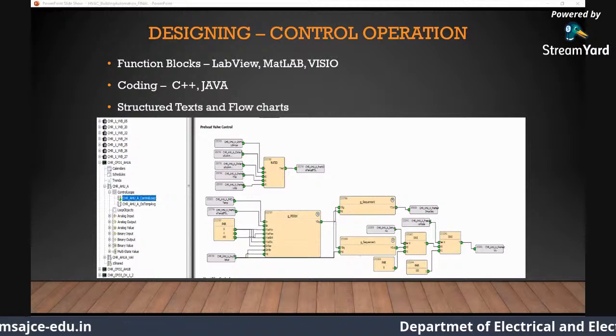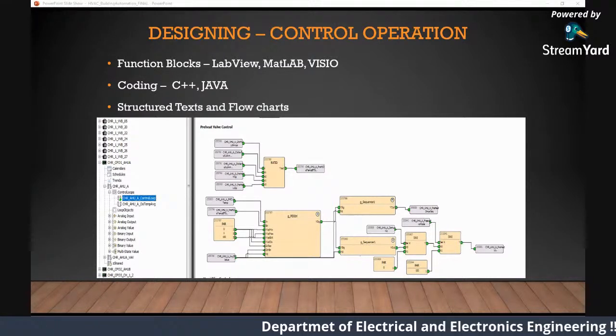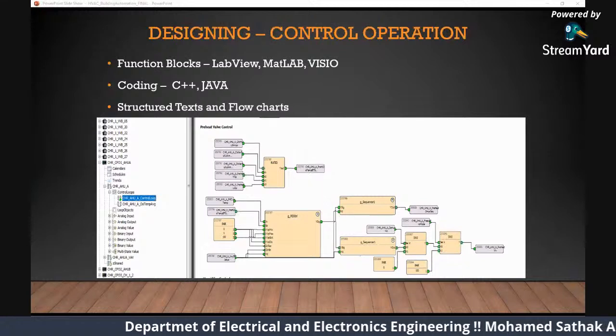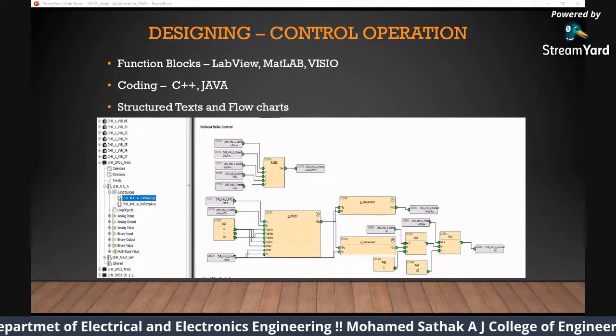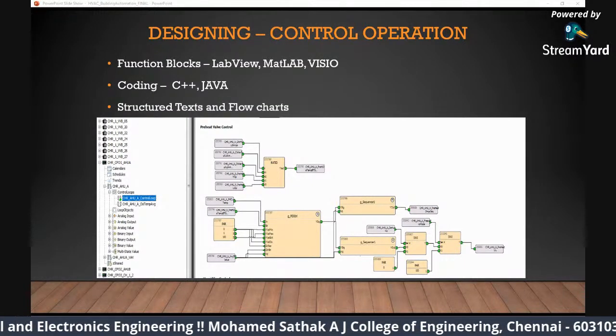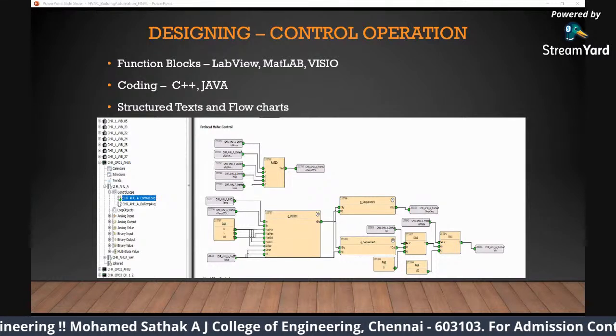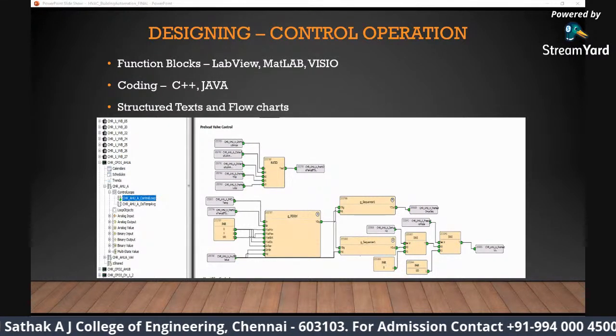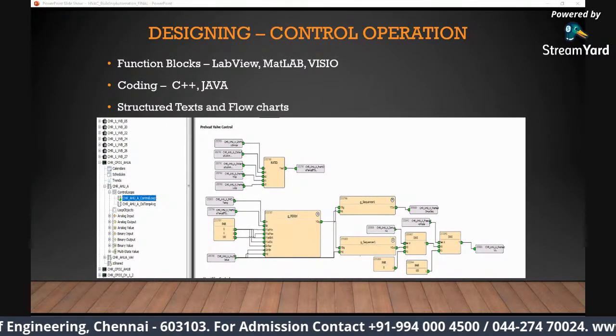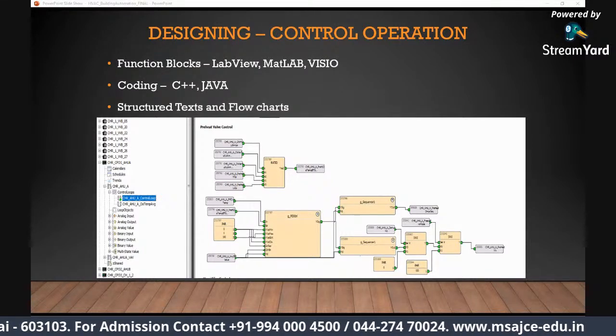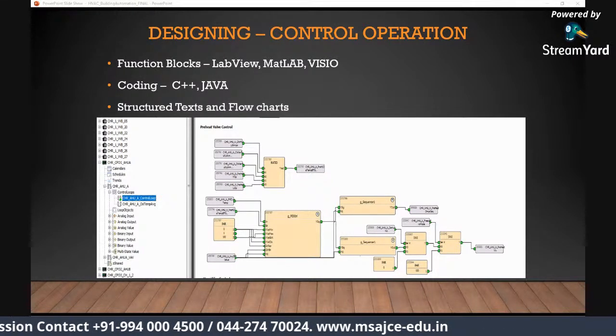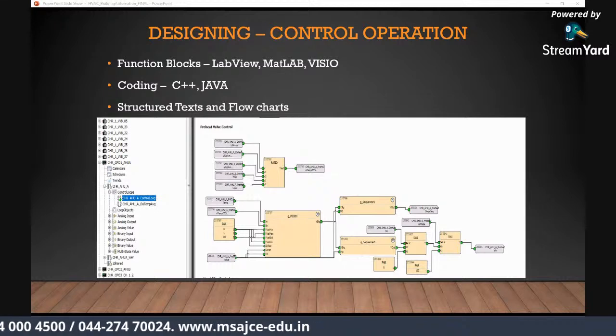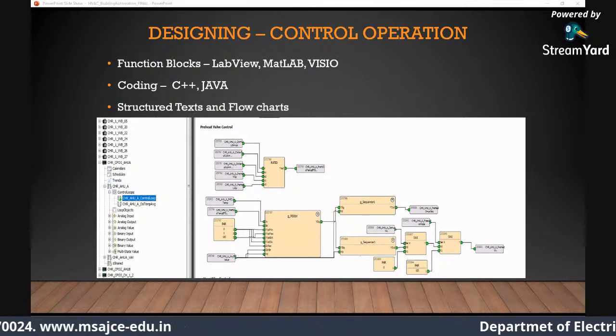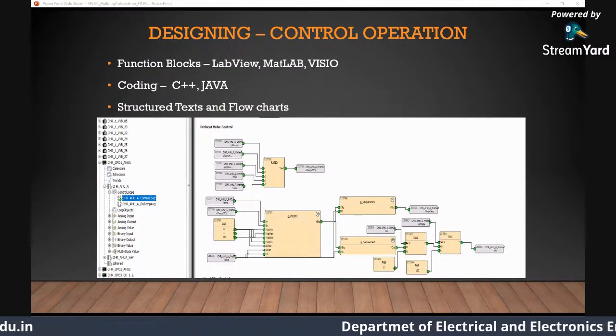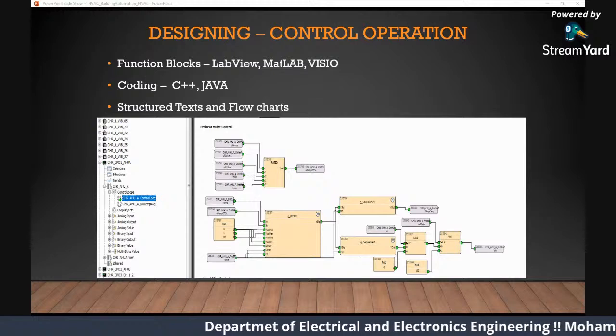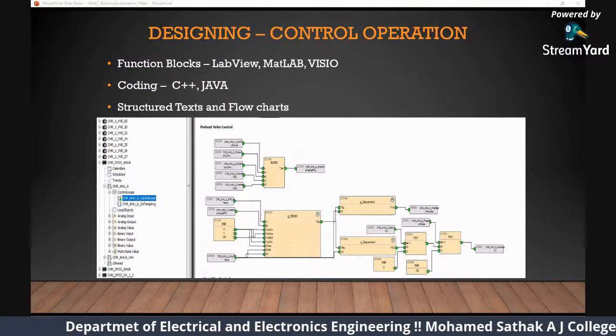Not every building will have one AHU, one chiller, and one boiler. There are huge campuses. I've dealt with sites where there are 20 buildings, 30 buildings. They will have 10, 15 chillers, 30, 40 boilers, 10, 15 AHUs. So they run on a duty standby basis. If the load is more, we call it building load, right? You should have heard the term tonnage, 1 ton, 1.5 ton. That's the refrigerant measuring capacity of your chiller. Let's say there are two, three chillers in your building. If the load is more, if there are more people coming in, they'll turn on more chillers.